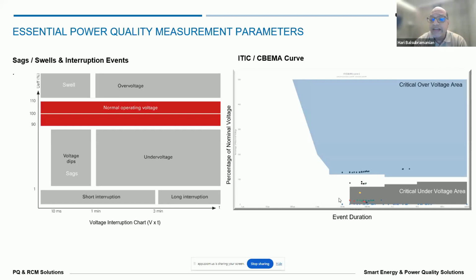On the right side of the screen, I have something called ITIC. The ITIC curve is again a standard which gives a nominal voltage working performance and the critical voltage areas. The x-axis is the time and the y-axis is the percentage of the nominal voltage. If there is an event within the critical voltage area, whether it is over voltage or under voltage, then we can find out how many events are happening in the over voltage area and how many in the under voltage area.